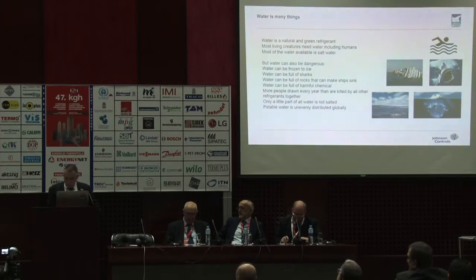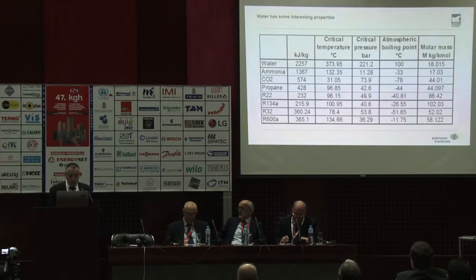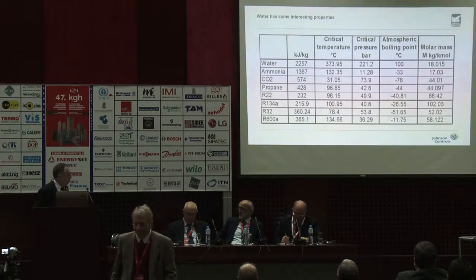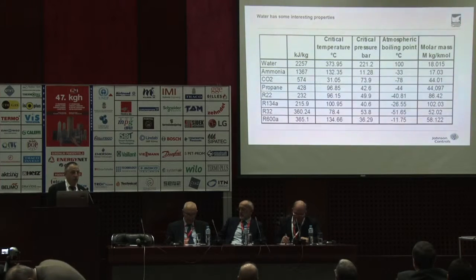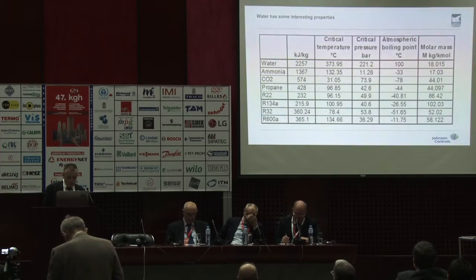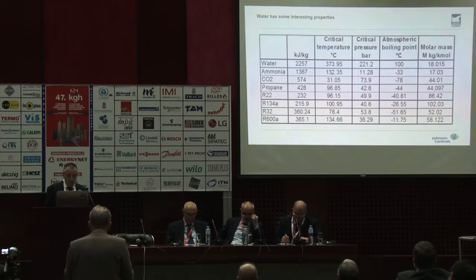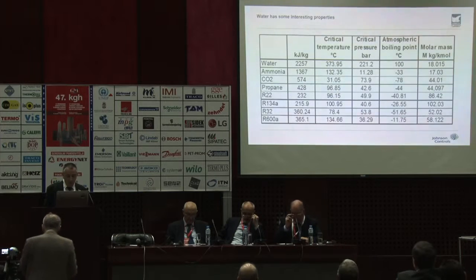Just a few points about water. But if we use it as a refrigerant, it has a lot of other properties which are very good. A lot of you have learned a lot about water, probably during your studies. We know that the evaporating heat of water is about 2,256 or 2,257 kilojoules per kilogram. It is twice as much as ammonia, so it could indicate very low flows. But there's no need to go as low as 18 grams per kilowatt because it's quite a safe refrigerant.